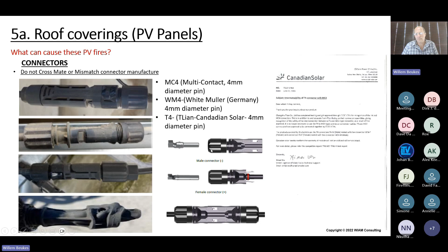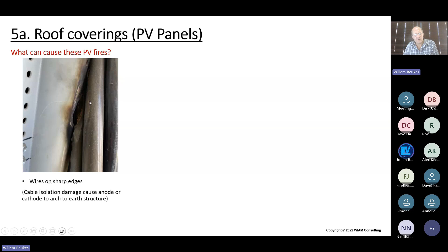In a lot of areas, we have sharp edges, for example, on the DC wiring, where the sharp edges eat up the anode or the cathode wiring and then form an arc where there's no earthing component on the structure. In most cases, insufficient ventilation causes these panels to overheat. In most of these installation manuals of the solar panels, you'll read that when you install these panels, they need to be a minimum of 100 mm below the panel for ventilation purposes, so that these panels can ventilate and cool down. Even on the edges, for example, of these panels, you need to have a minimum of 6 mm gap so that this heat can escape between large areas of panels where they are in an array.